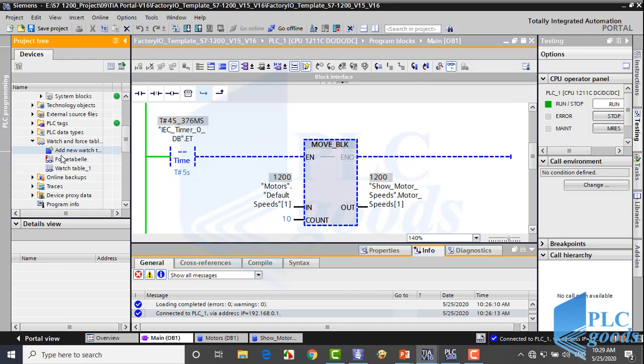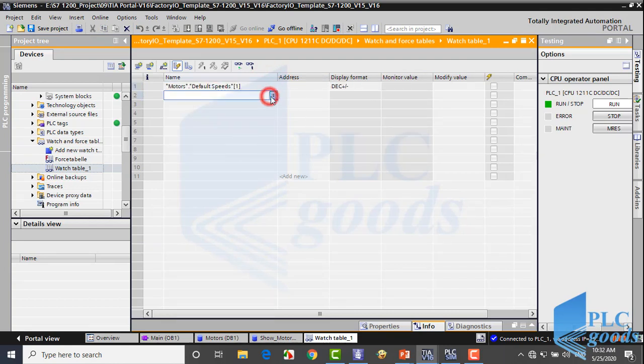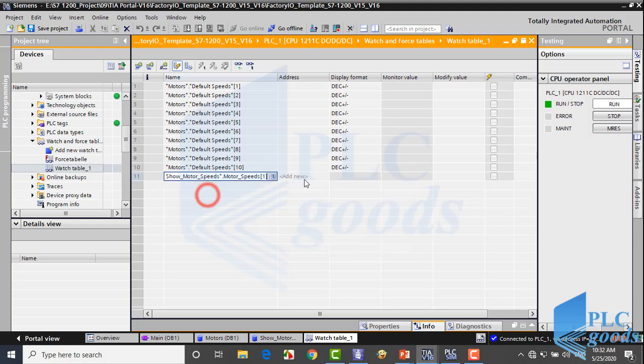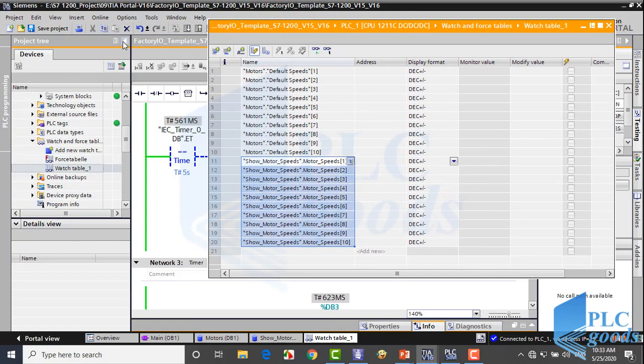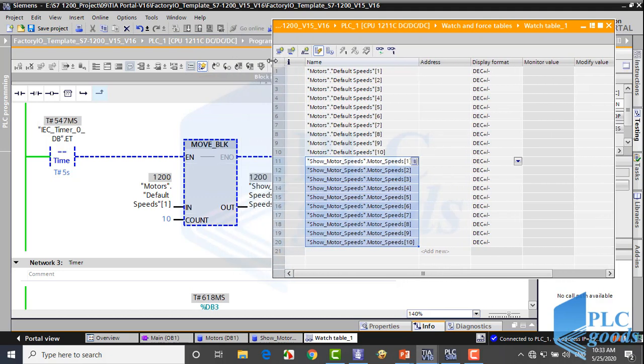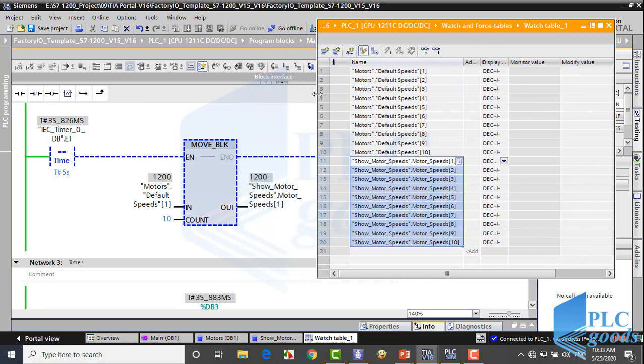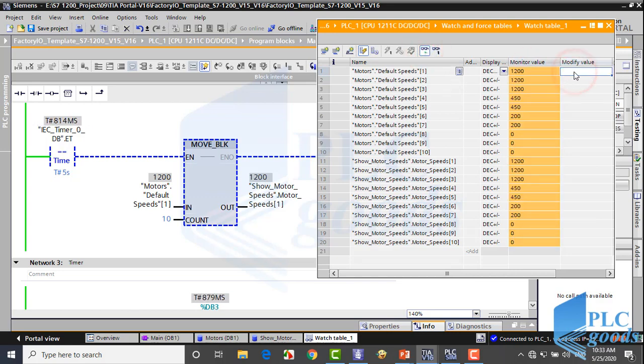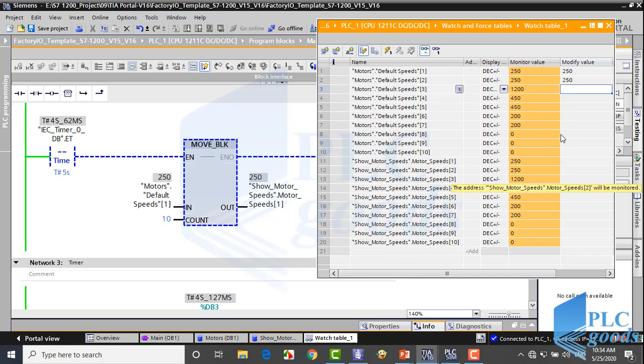Let me open a watch table. Here, first I insert the motor speed array from the first block, then I insert the second array. Let me have a better view. Click here to monitor all array values. Now let me write another speed value at this column. I click here to modify speed values. As you see, this program is updating the speed value of the second array every 5 seconds.